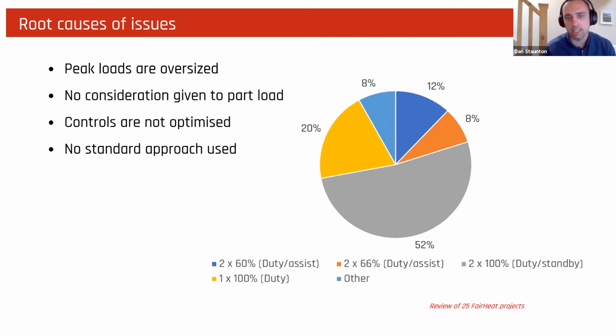We had a quick look at the last couple of years' worth of designs that have used plate heat exchangers, from other consultants and clients. Around 50% used a duty standby approach, 20% used a duty single plate approach, another 20% used the duty assist approach, and 10% just other designs. There's no clear standard being used, and that's preventing lessons learned being taken forward into the commissioning and specification of plate heat exchangers and control valves moving forward. And that was the purpose of Lucy's project.